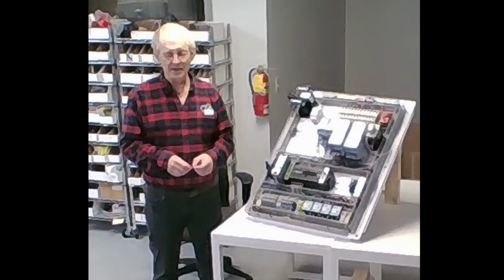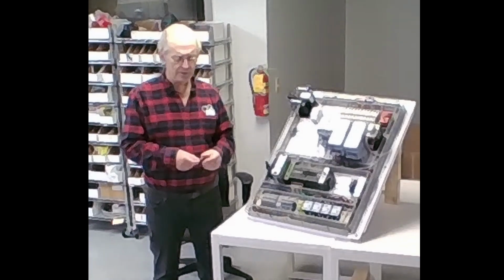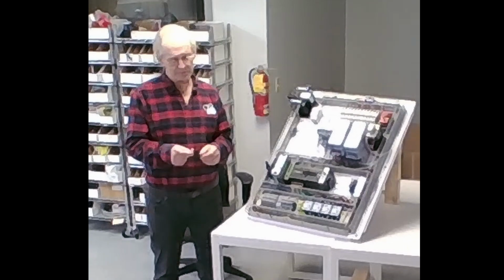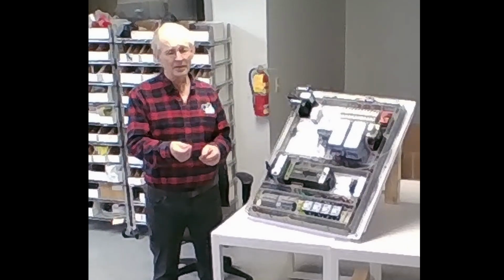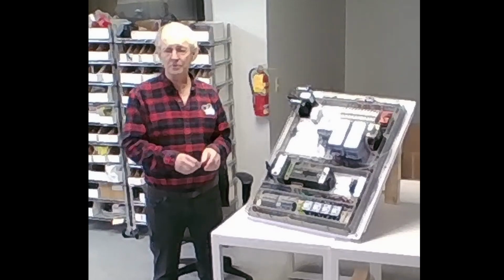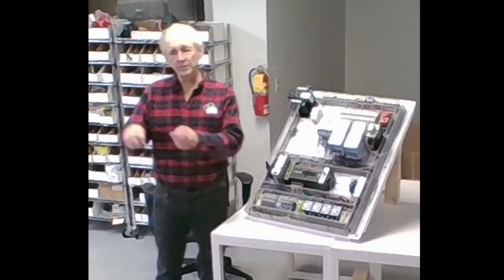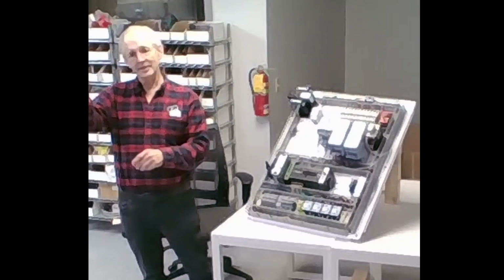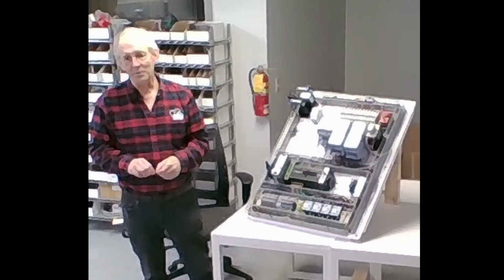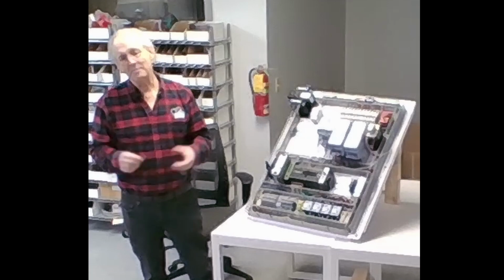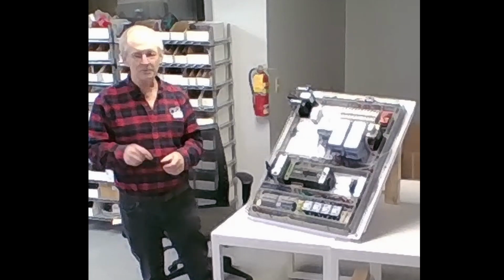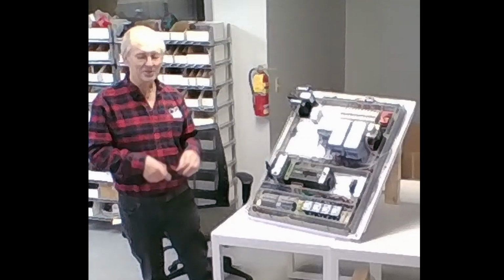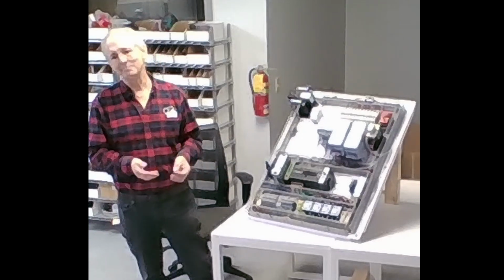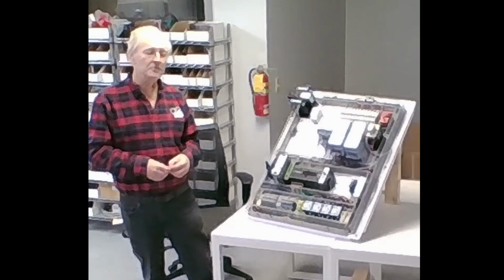I said, "The motor didn't go bad. The fuse blew the motor." He said, "What do you mean?" I said, "Well, they turn blue like that when they get hot. Copper turns blue. So one end of that fuse was getting hot." So we opened up the main switch, and sure enough, the fuse block was all burned up. So what was happening was his motors were being burned out by the fuse blowing and single phasing the motor, and then the motor would trip.